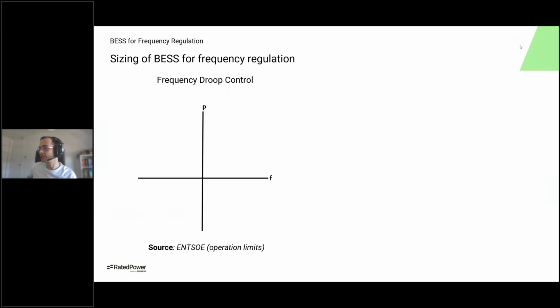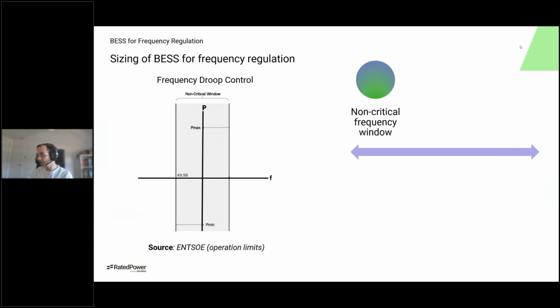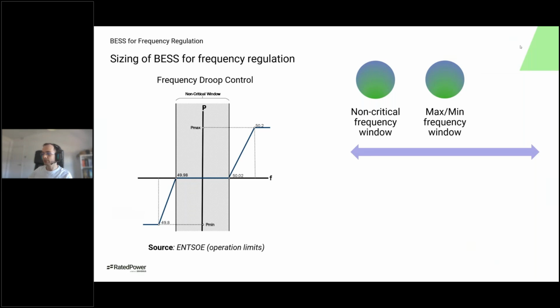So given this PF chart right here, we have to define what we call the non-critical frequency window. This is a window where the battery system will not do anything. It will not charge or discharge. We don't want it to turn on and off constantly just by really, really small deviations. So we have to define this non-critical frequency window. Then we have to define the maximum and minimum frequency window. In these windows of operation, we will ramp up or ramp down the generation of the batteries linearly, depending on the frequency deviation.